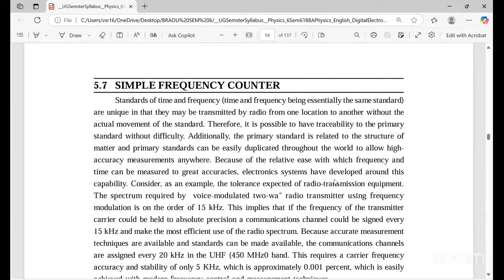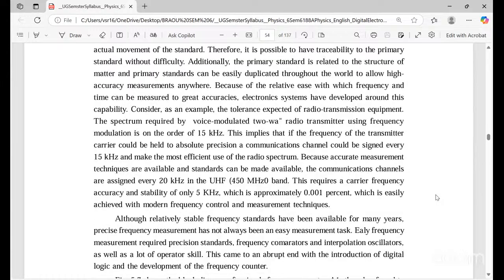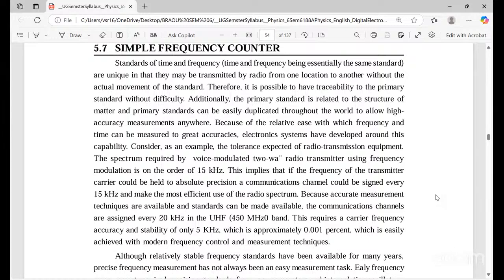Next is the simple frequency counter. So here, standards of time and frequency are unique in that they may be transmitted by radio from one location to another without the actual movement of the standard. Therefore, it is possible to have traceability to the primary standard without difficulty. The primary standard, which is related to the structure of matter, can be easily duplicated throughout the world to allow high accuracy measurements. Because of these reasons, frequency and time can be measured to great accuracies.